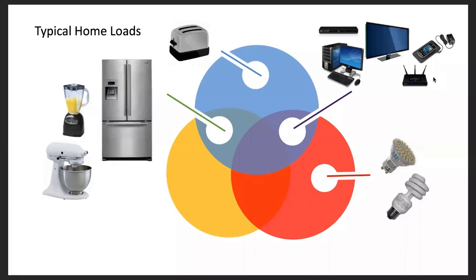You get one for $150 to $200. The basic home floor mount UPS will filter out all those transient voltage spikes and protect the big battery from having any nuisance trips, as well as provide the added benefit of protecting these loads from the 4-second transition from grid side to off-grid mode. There's a 4-second delay when the grid goes down before the battery will kick in backup mode.